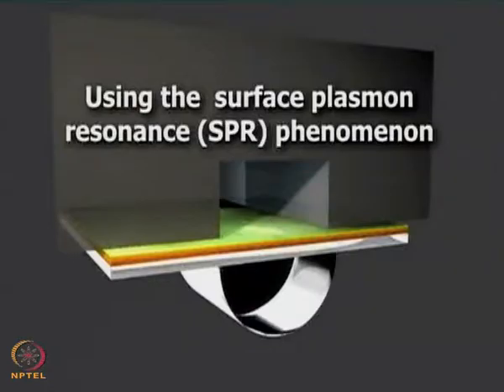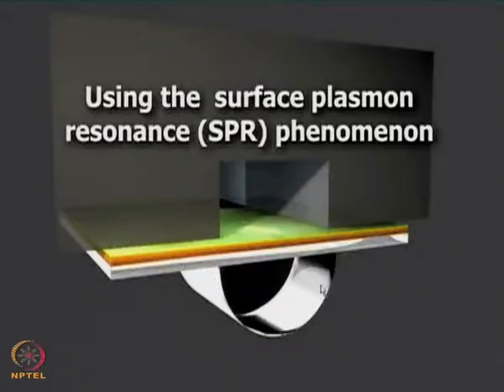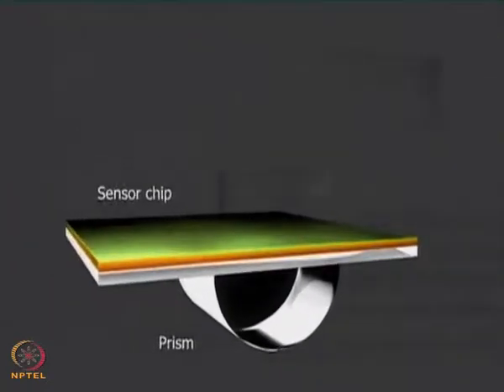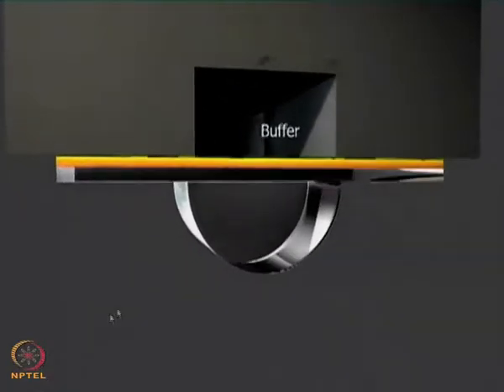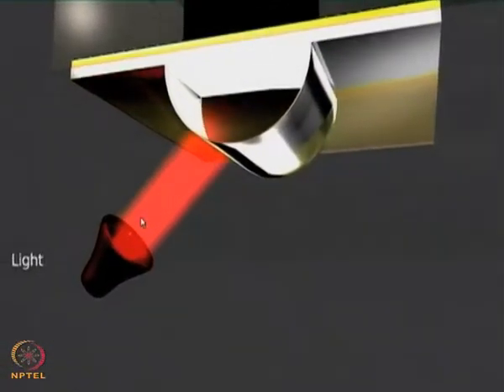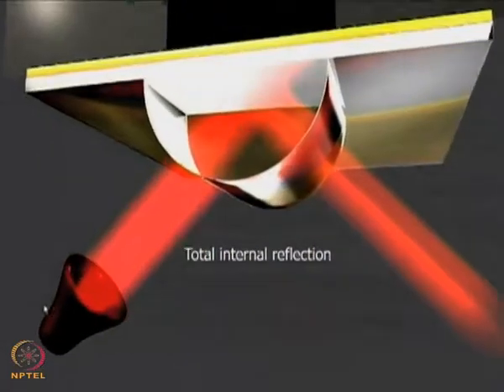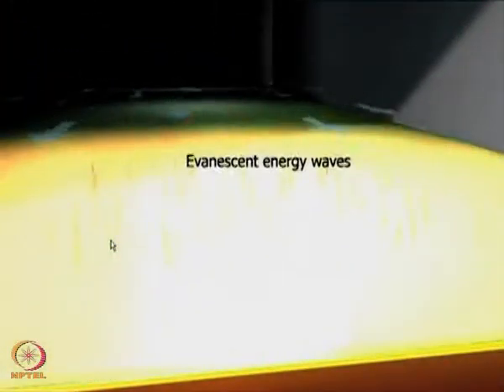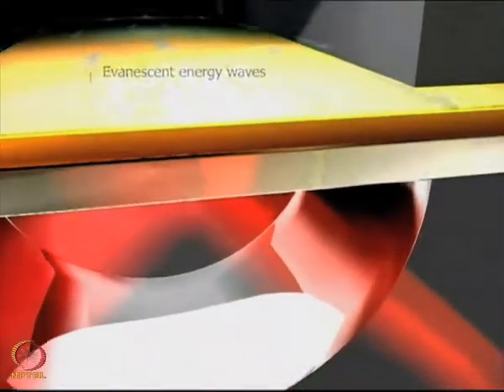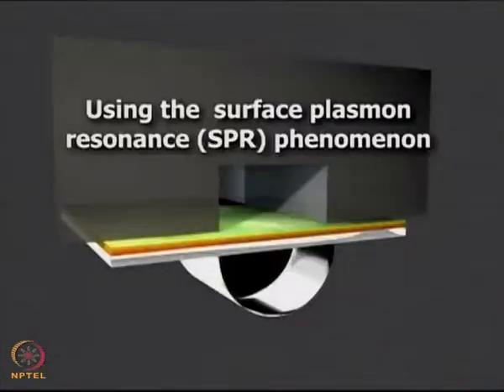What I show here is the basic SPR phenomenon. This is the SPR chip. On top of the SPR chip is a gold layer, and on top of it is a flow cell. At the bottom you see a hemispherical prism. The SPR phenomenon is pretty simple: when you have the prism and you shine a laser light through it, the light reflects at the angle of total internal reflection. Evanescent energy waves are created on top of the chip, and these evanescent energy waves are also called surface plasmons. These surface plasmons are the ones used to actually study biological interactions.